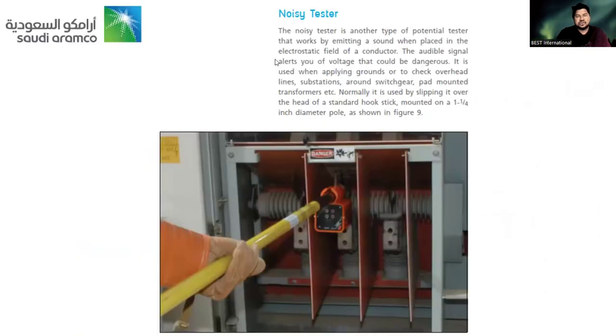The same with the noisy meter, which should also be there, because the noisy tester is another type of potential tester that works by emitting a sound when placed in the electrostatic field of a conductor. The audible signal alerts you of voltage that could be dangerous. It is used when applying grounds or to check overhead lines, substations, around switchgear, pad mounted transformers. Normally, it is used by slipping it over the head of a standard hook stick. Look at the picture actually. Okay.